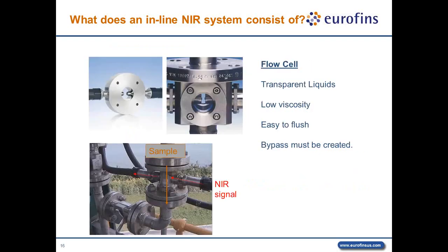The fiber optic probes give us the ability to scan the material in line without having to pull a sample. They come in a variety of shapes, sizes, and configurations. However, the three main categories are the flow cell, the insertion probe, and the sensor head. The flow cell is great for transparent liquids with low viscosity. A bypass is created, and the two fibers that extend from the source and back to the detector can be positioned in the cell with the proper path length.